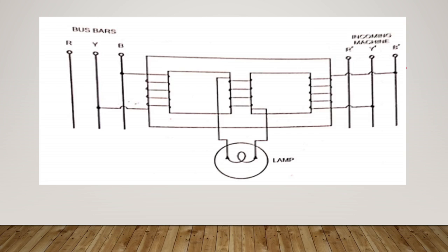So now let us see the terms synchronizing current, synchronizing power, and synchronizing torque. Once a synchronous machine is synchronized, it will tend to remain in synchronism with the other alternators. Any tendency to depart from the condition of synchronism is opposed by a synchronizing torque, which is produced due to circulating current flowing through the alternators.